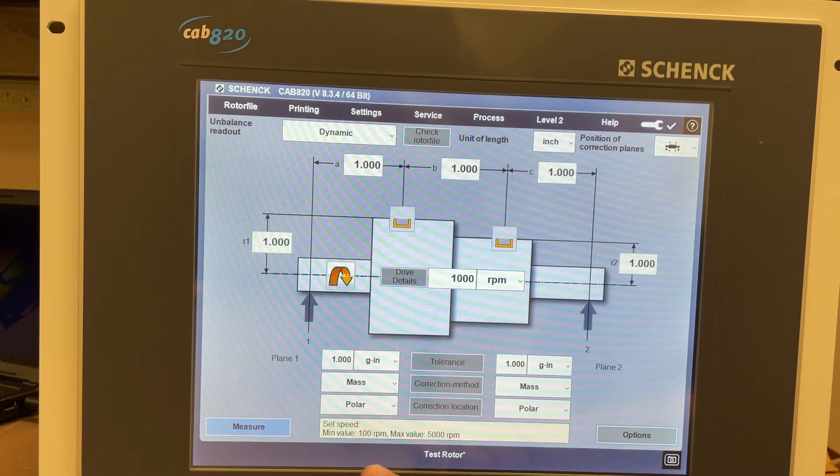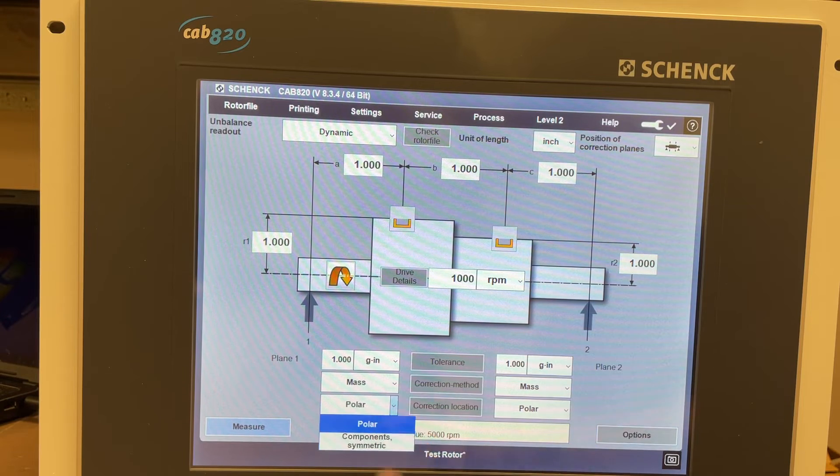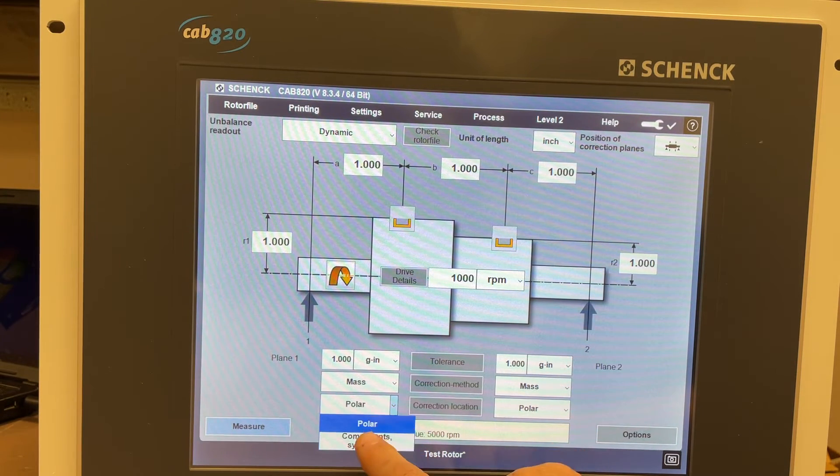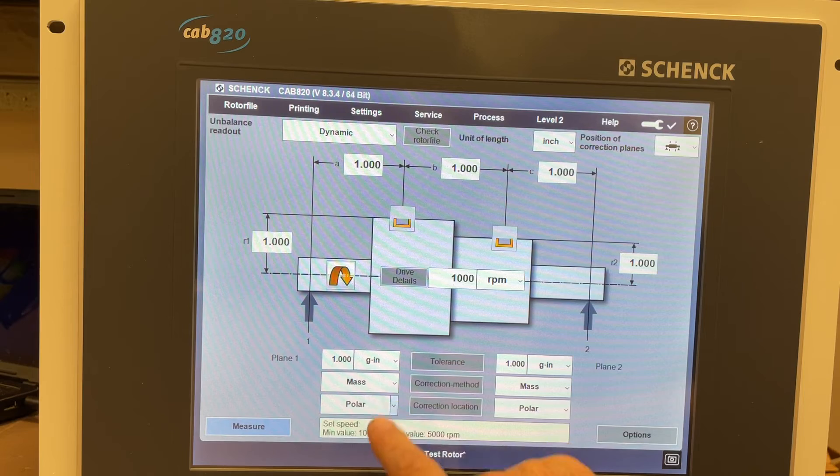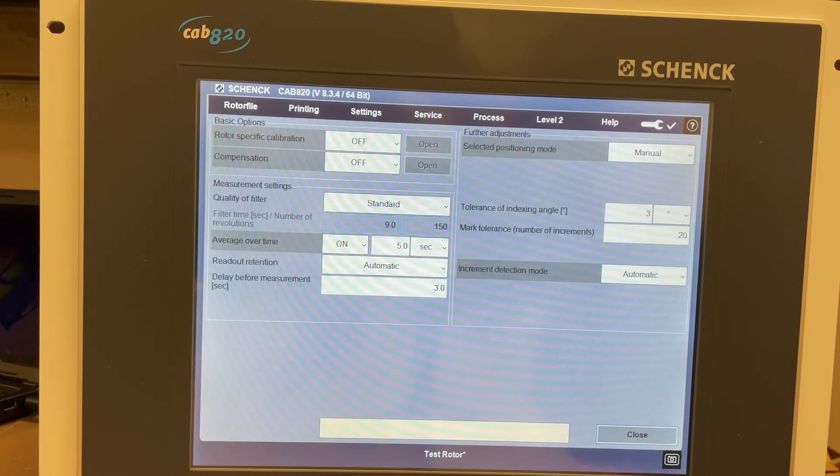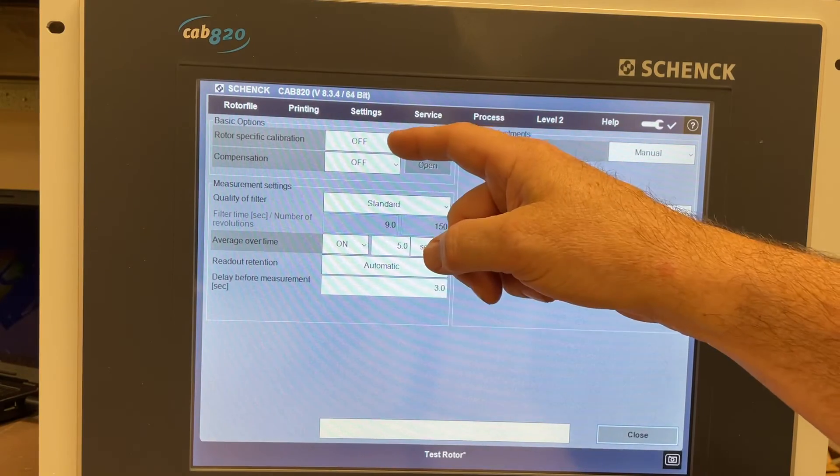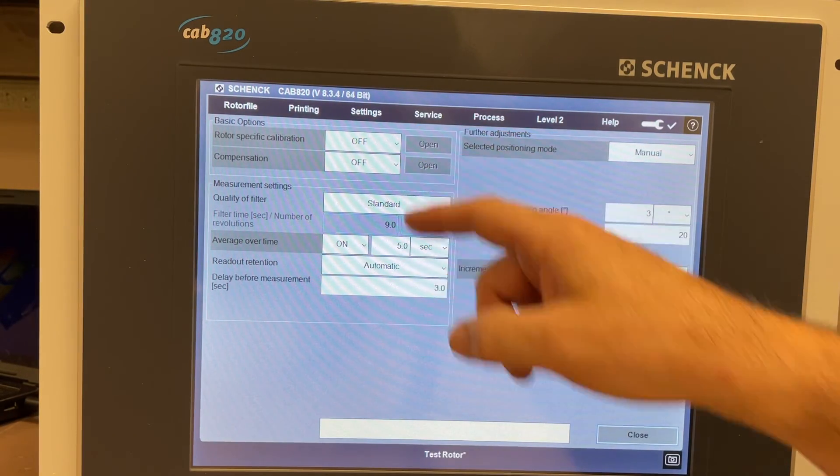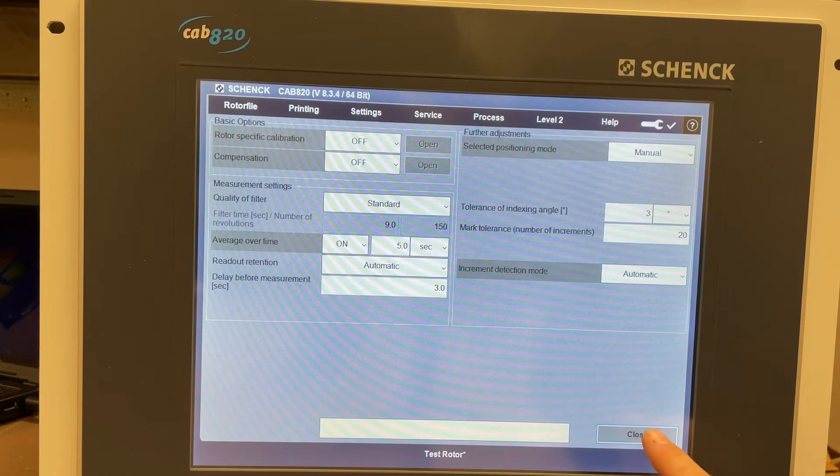You can go in to look at polar, you can do components instead of polar. You can look at options in here. They've got where you would turn on the rotor-specific calibration and the compensation. This is where you would actually turn them on in the software.